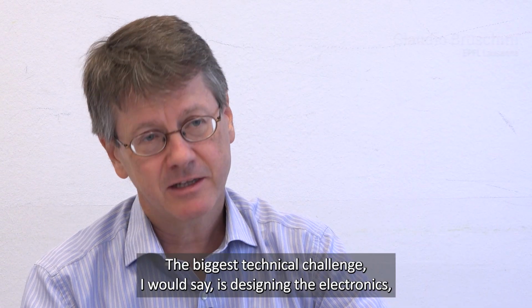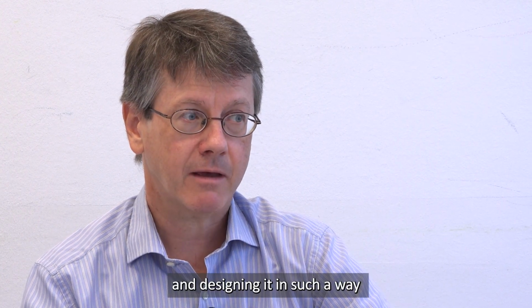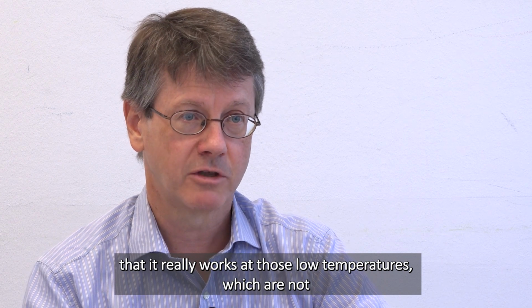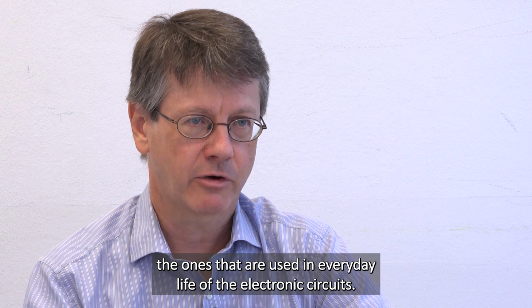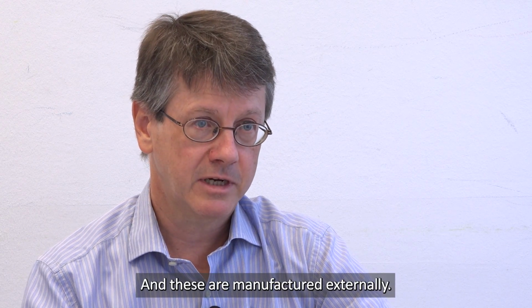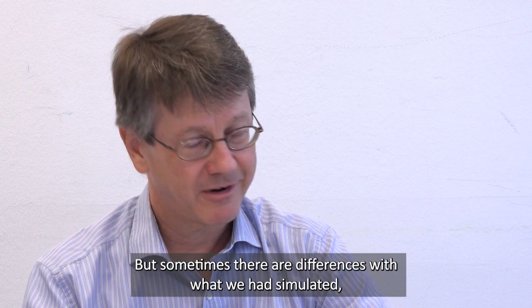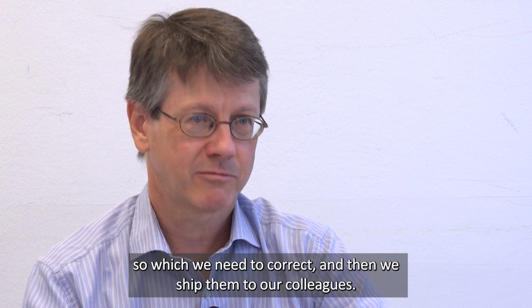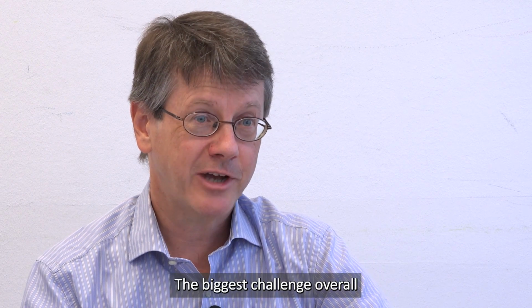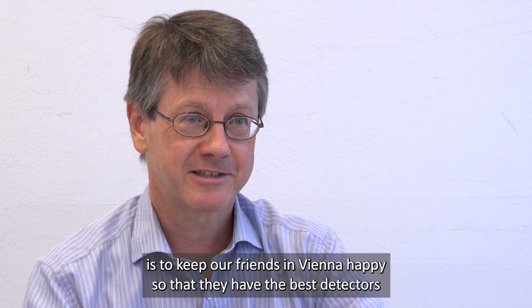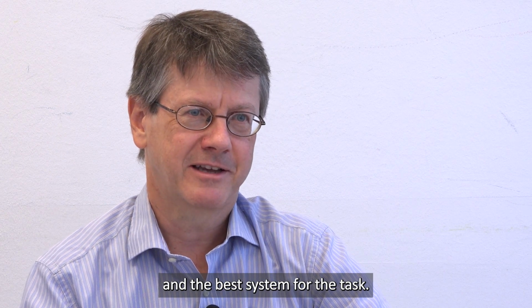So the biggest technical challenge, I would say, is designing the electronics, which is done with specialized software, and designing in such a way that it really works at those low temperatures, which are not the ones that are used in everyday life of the electronic circuits. Then these are manufactured externally, they come back to us, we test them, we integrate them, but sometimes there are differences with what we had simulated, which we need to correct, and then we ship them to our colleagues. The biggest challenge overall is to keep our friends in Vienna happy so that they have the best detectors and the best system for the tasks at hand.